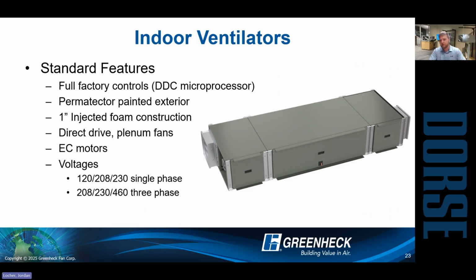Some of the standard features we included on this new indoor series: it is full factory controls, so we're always doing that microprocessor controller. We chose to do a Permatector painted exterior. We tend to find just a little bit nicer fit and finish with that. And this is also a 1-inch injected foam construction, so a little bit more premium in that sense on the DOAS side of the market. And then across the board, direct drive plenum fans using EC motors. We do have single phase and 3 phases available in both cabinet sizes and both with the ERVI and IVE with electric heat. So whatever your voltage, whatever your project, there's a lot of great options here for that very high efficiency project.